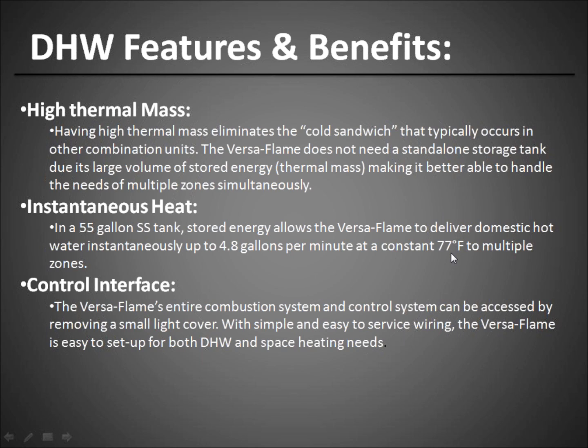The control interface, the VersaFlame's entire combustion system and controls can be accessed from the front with very simple and easy service wiring. The VersaFlame is easy to set up for both domestic hot water and space heating. One of the things I want to point out, which we'll go over the diagram of the appliance, is the control is the same as what we're using on all of our appliances. The fan, the system setup is all the same. Basically, it's the same as the Pioneer. We're just putting the DHW pack on the top.